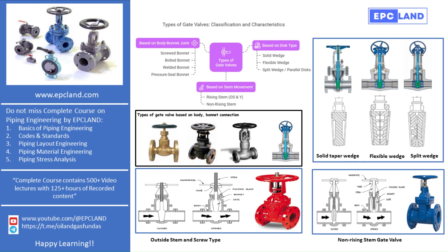The welded bonnet type is used when there is no need to open the valve for maintenance. It is lighter in weight and provides a permanent seal. The pressure seal bonnet design is used for high pressure and high temperature services. The higher the pressure inside the valve, the tighter the seal becomes.